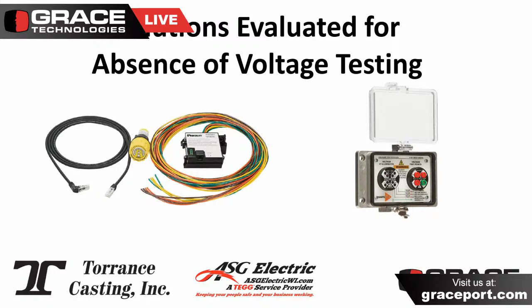As we evaluated that, the device itself is a more complex installation than the voltage test station from Grace. It requires installing two terminations or leads, some distance apart, on each phase, plus a whole other module installed in the door, which connects to an internal control box, and from there out to the different points of monitoring or sensing, like terminating a sensor wire.